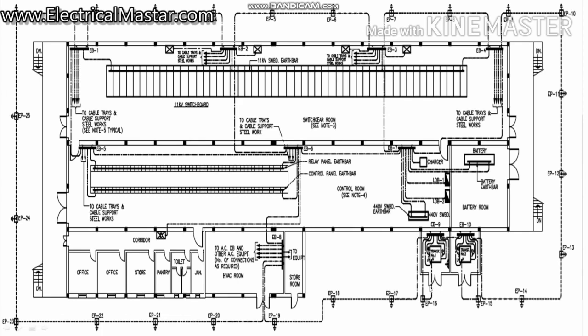EP16. For the neutral wire they used 120 square mm copper bare conductor, and from the earth pit to the earth bus bar they are using 70 square mm. Okay, so from the earth bus bar to individual components like the body of the switchgear and battery charger, heavy equipment like the transformer body, they normally use 35 square mm PVC coated yellow green cable. For the lighting DBs, from the bus bar to the lighting DB they use maybe 10 square mm PVC coated yellow green cables.